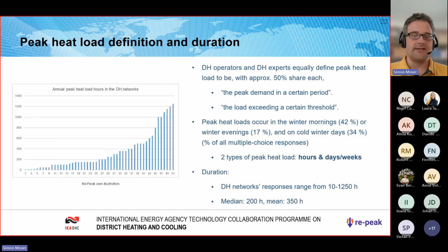Given this diversity of peak heat load definitions, the district heating network responses range from 10 hours peak heat load per year to 1,250 hours per year, with a median of 200 hours and a mean of 350 hours of peak heat load. But that definitely also makes a big difference, especially when we talk about the choice of how to cover peak heat loads ideally and what option to choose, because when you have 10 hours, the answer is probably different from the situation when you have 1,250 hours.